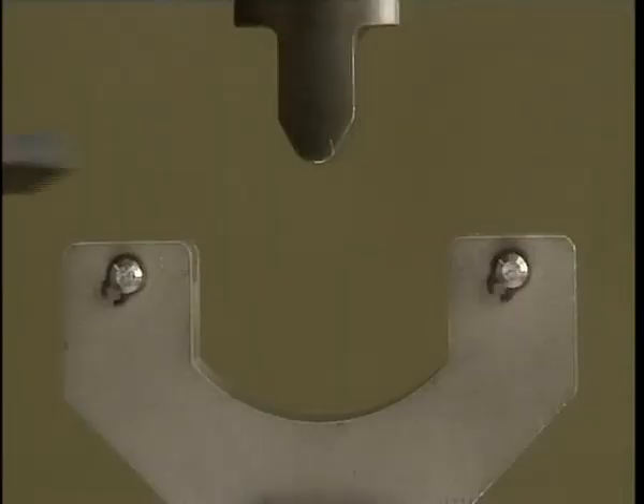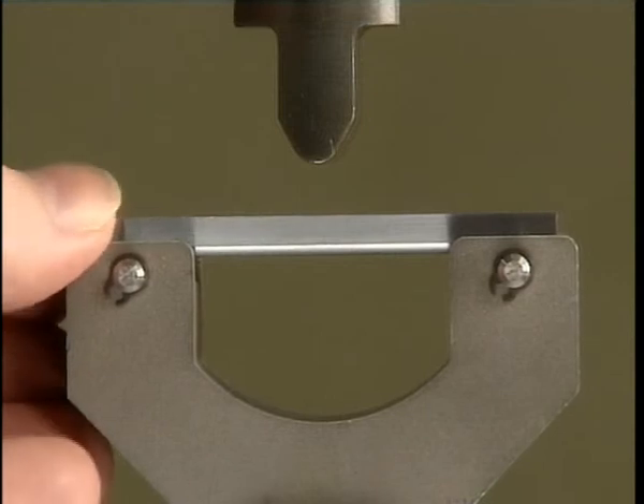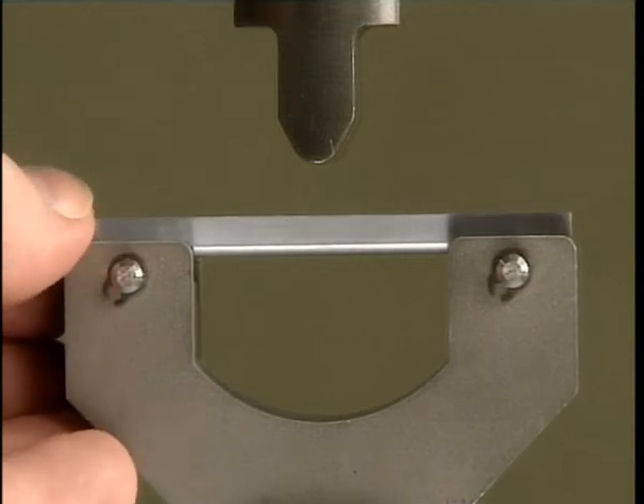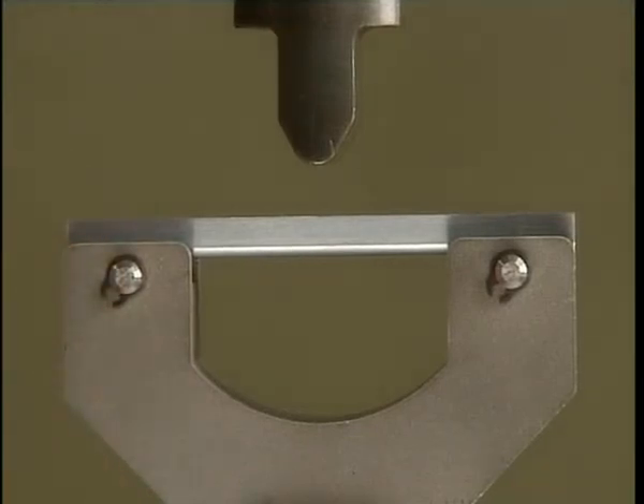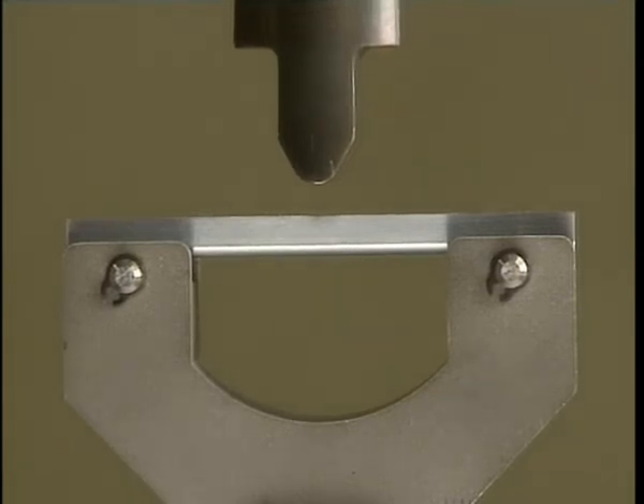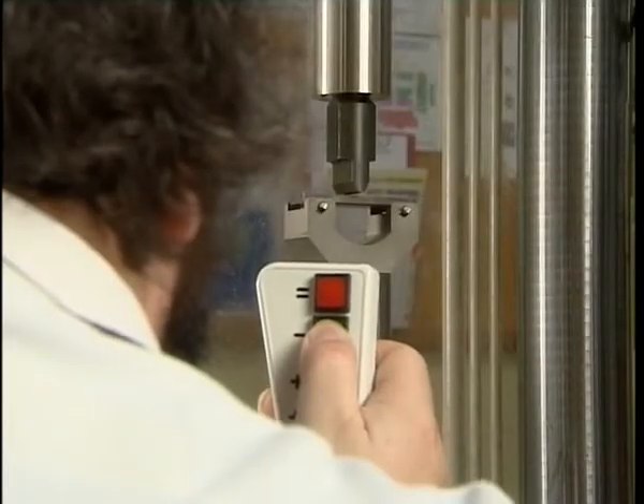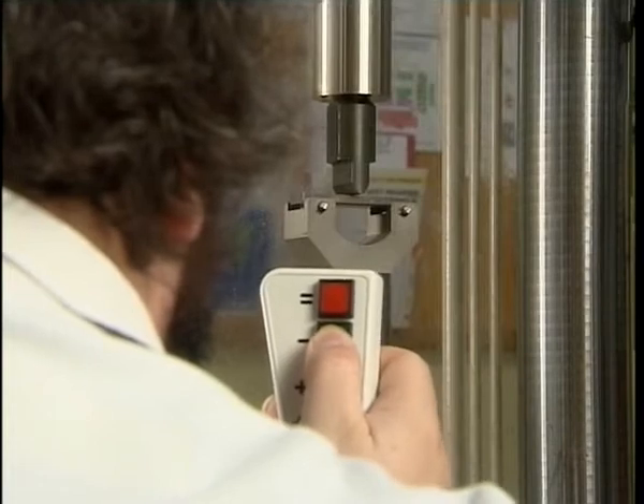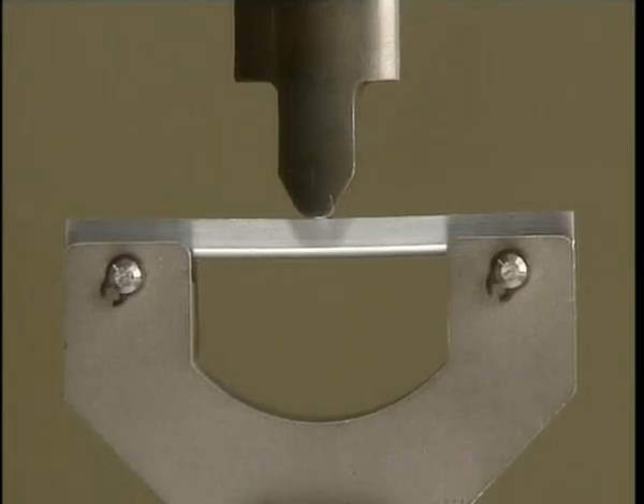Now position the test piece onto the number 2 and 3 rollers. Once I've got it positioned, I have to bring down the number 1 roller until it's in contact with the test piece. Once it's in contact, I can start the test.